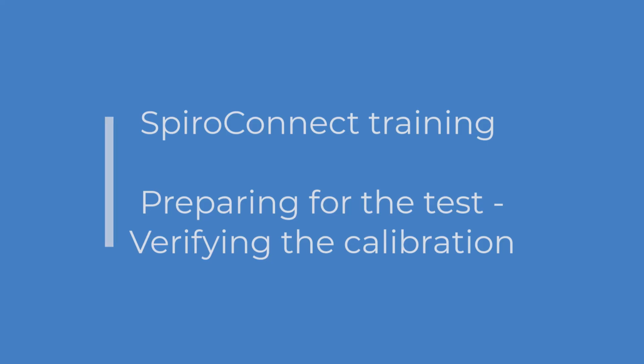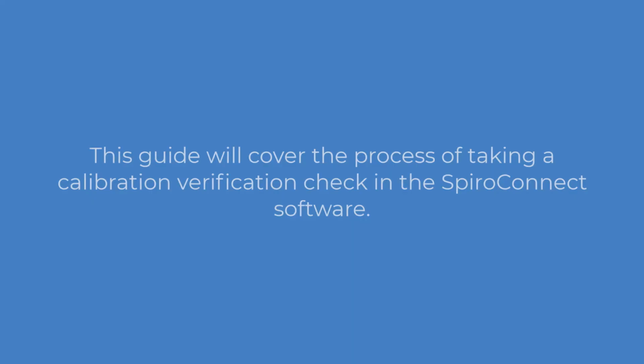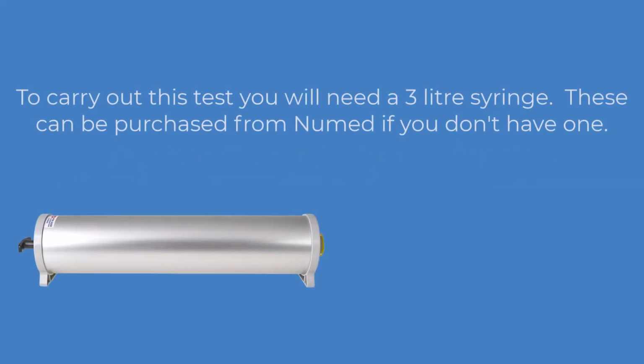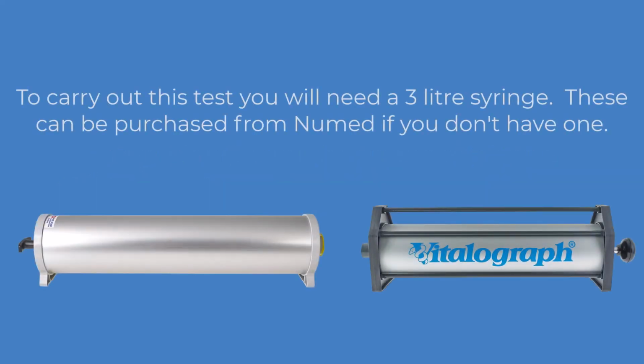Preparing for the test, verifying the calibration. This guide will cover the process of taking a calibration verification check in the SpiroConnect software. To carry out this test, you will need a 3-liter syringe. These can be purchased from Numed if you don't have one.